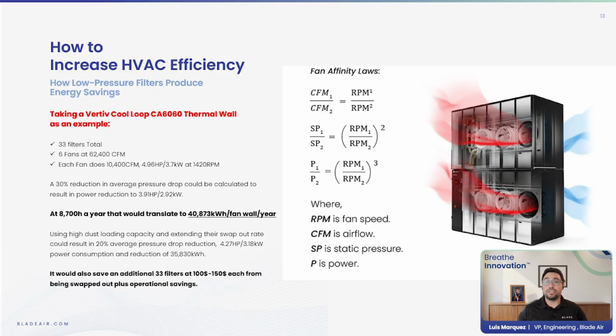Now, a different approach could be to extend the filters to 6 months because they have a higher dust holding capacity. That'll reduce your average pressure drop to maybe only 20% instead of the 30%, but it helps to remove 33 filter swap outs, and each one of these filters costs maybe $150 each, and it reduces the downtime from having to switch the actual filters. All of that is in addition to 36,000 kilowatt hours saved. So you're saving on the energy usage, you save on the downtime, and you're able to save the actual money from having to buy more filters. This is just to illustrate the potential savings that could be missed from not optimizing the filter system and using high dust holding filters to maximize the efficiency of the entire system.